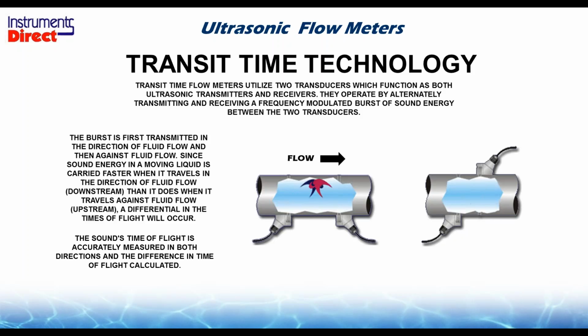An ultrasonic transit time flow meter is clamped on the outside of the pipe, and it measures flow using ultrasonics. In this picture in the middle, I have a diagram that says the flow is going from left to right. I take a sound burst from this transducer, shoot it across the pipe, ricochet off the back wall, come downstream to this sensor here, and I measure how long it took to get from the first sensor to the second sensor. Now remember, the flow is going left to right. I'm going to take this transducer and send a sound burst across the pipe to this sensor, but I'm going against the current, so it takes a longer period of time to transit from one transducer to the next.